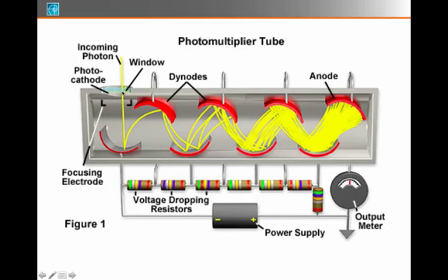When the photon hits that material, that photocathode as it's called, an electron is ejected and is accelerated downward toward this U-shaped piece of metal. And when that electron hits that metal, it makes the metal eject another electron, and it's accelerated over to another small piece of metal over here, which is held at an even more positive voltage. And now that one electron comes in and hits that piece of metal and makes two electrons, the original plus one more that's ejected out of the metal.